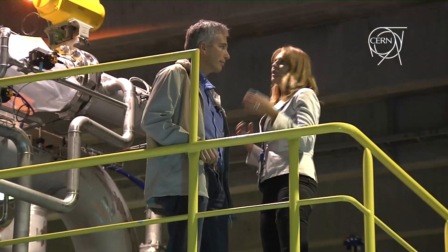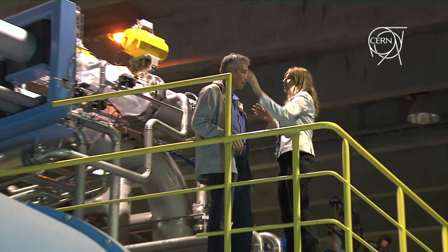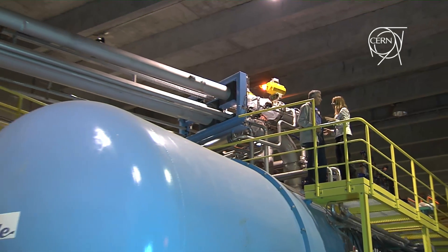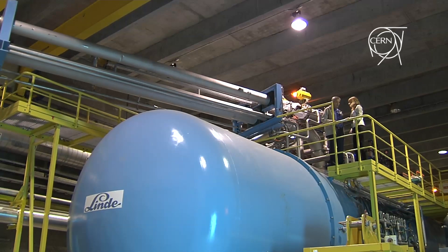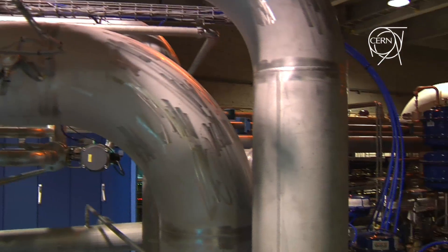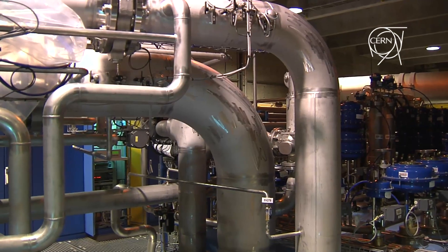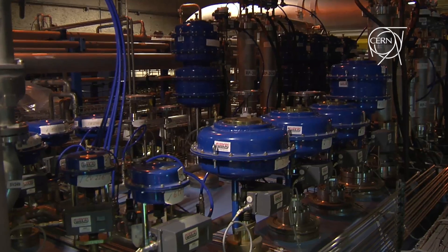Following the itinerary of helium, from the big tank through the compressor, we get to this other major installation. This is one of the eight helium liquefiers we have around the LHC — one per sector. The objective of this machine is to take helium at ambient temperature and liquefy it at a bit higher than four degrees from absolute zero, so minus 269 degrees Celsius.